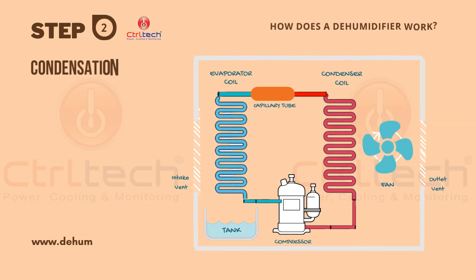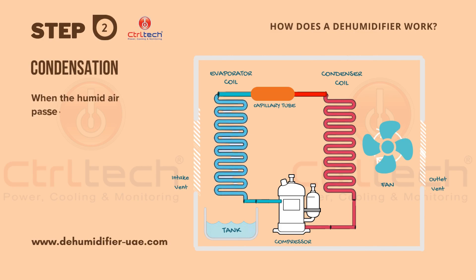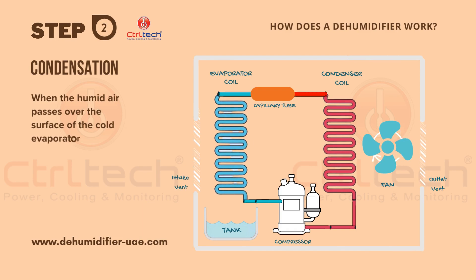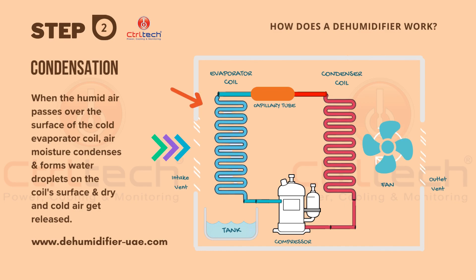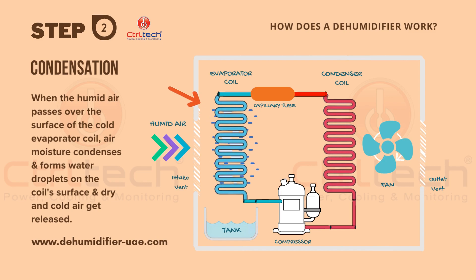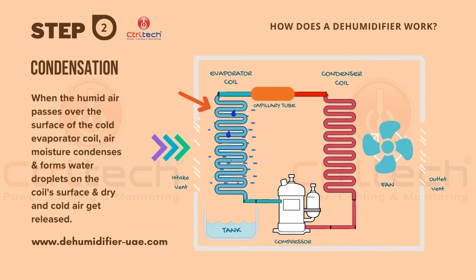In stage two, actual condensation happens and humidity from the air is removed. Due to the refrigeration cycle, the evaporator coil becomes very cold and its temperature becomes less than the dew point of the humid air — so it has a very cold surface. When humid air from the room is passed over the cold surface of the evaporator coil, the moisture present in the humid air condenses in the form of water droplets and accumulates on the evaporator coil. This process is called condensation, and in this stage the actual moisture from the air is removed.